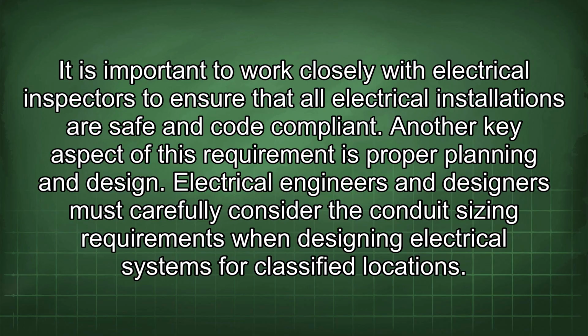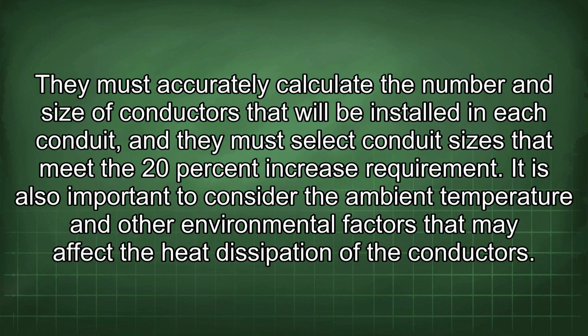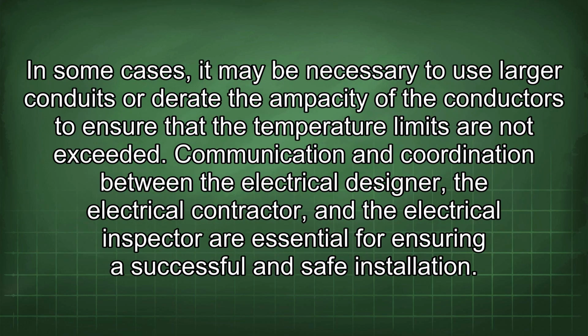Another key aspect of this requirement is proper planning and design. Electrical engineers and designers must carefully consider the conduit sizing requirements when designing electrical systems for classified locations. They must accurately calculate the number and size of conductors that will be installed in each conduit, and they must select conduit sizes that meet the 20% increase requirement. It is also important to consider the ambient temperature and other environmental factors that may affect the heat dissipation of the conductors. In some cases, it may be necessary to use larger conduits or derate the ampacity of the conductors to ensure that the temperature limits are not exceeded.